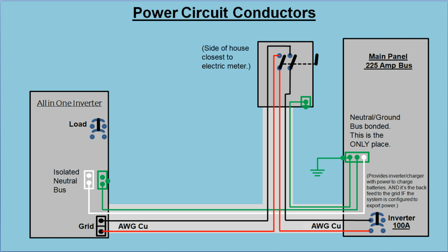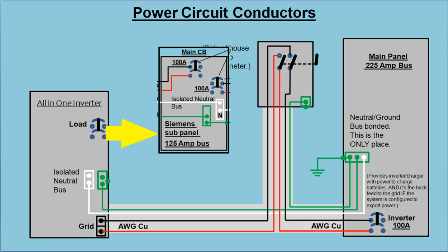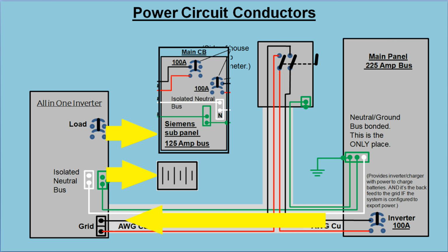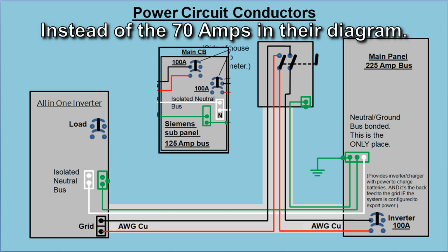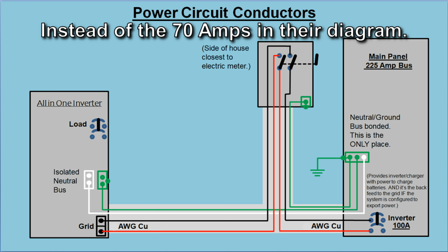The worst case scenario is when there's no solar power coming in and the batteries are dead. In this case, all the power going out to the loads is coming through the inverter, which is passing it through from the grid. And at the same time, the inverter charger might be charging the batteries as well, depending on how the firmware is configured. So this circuit would be carrying the charger current and the house loads as well. And what if the house load is 70 amps? How can these conductors carry enough current to charge the batteries? That's why I've chosen to provide a 100 amp circuit here, instead of the 70 amps in their diagram.